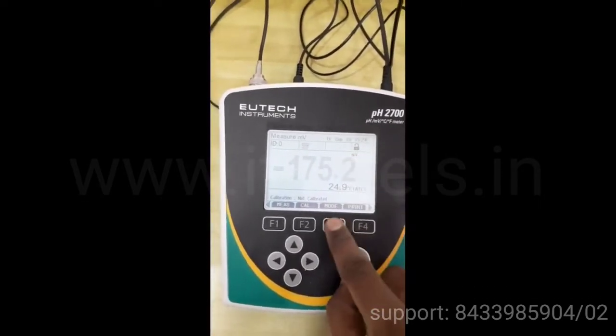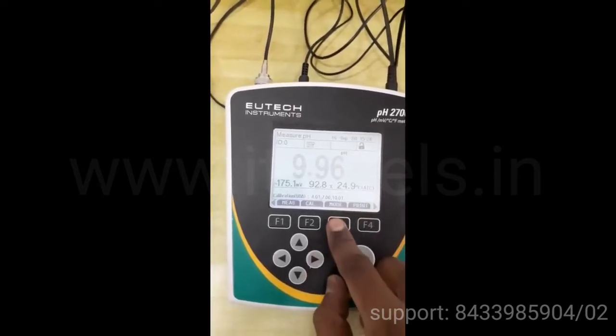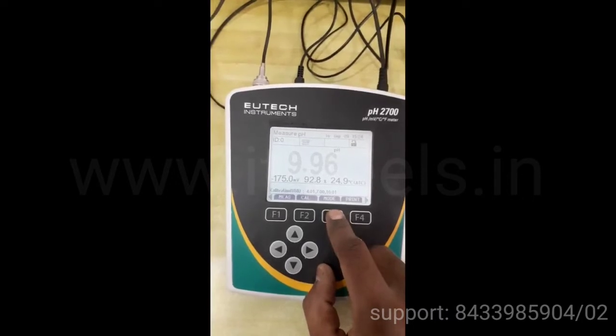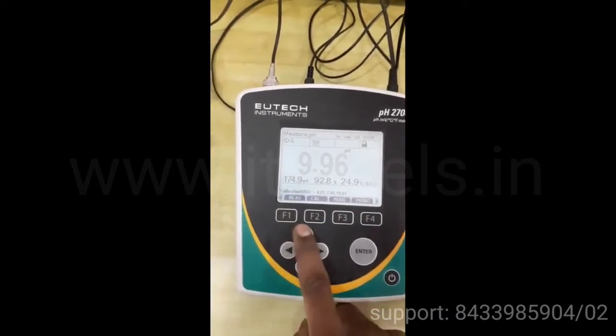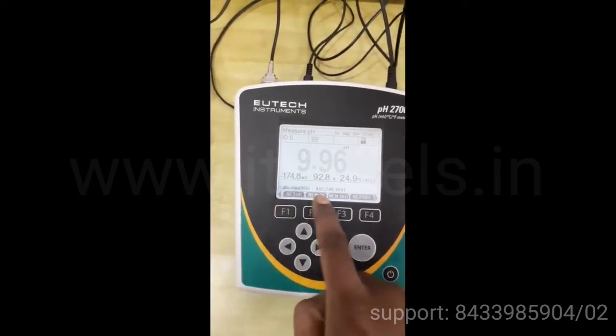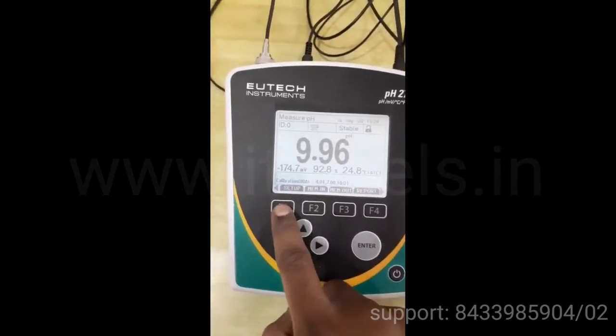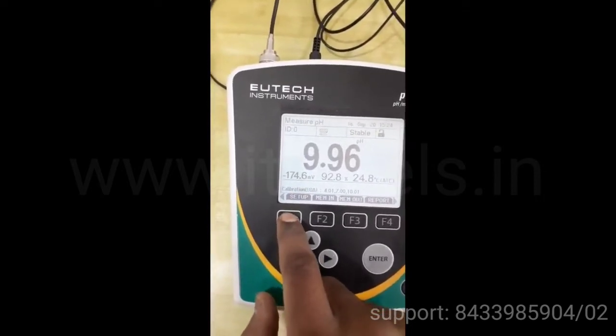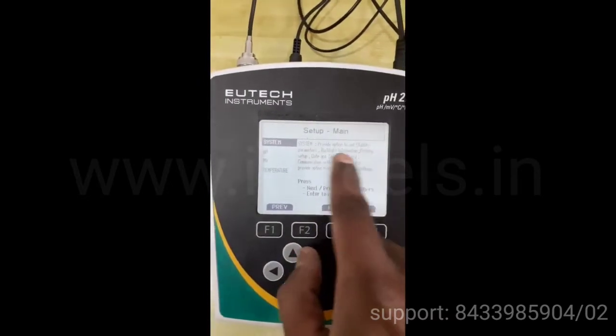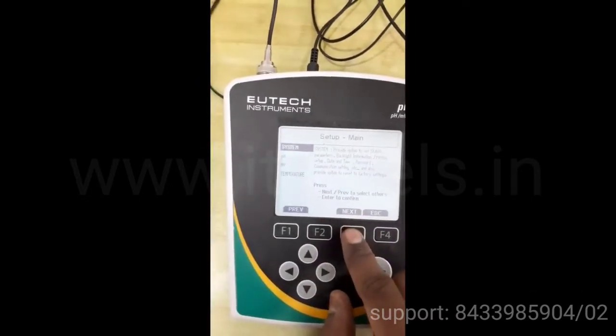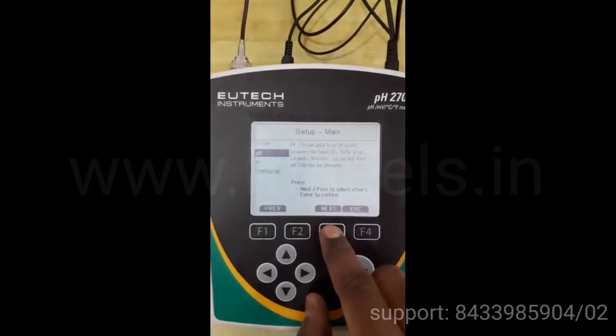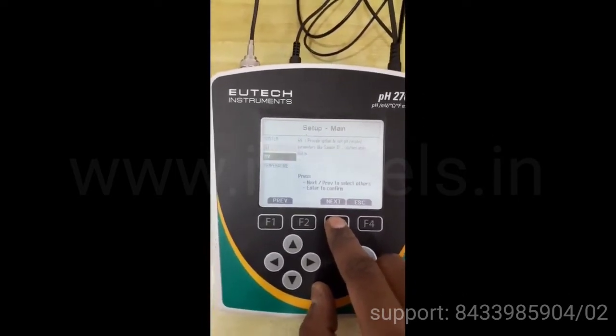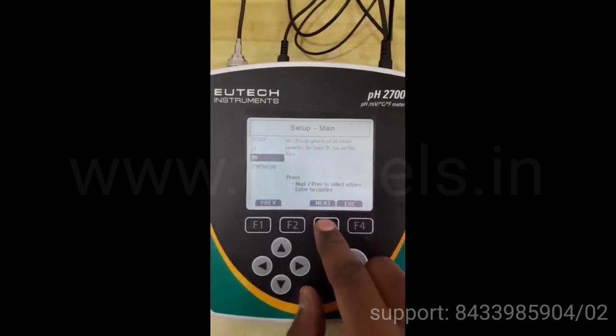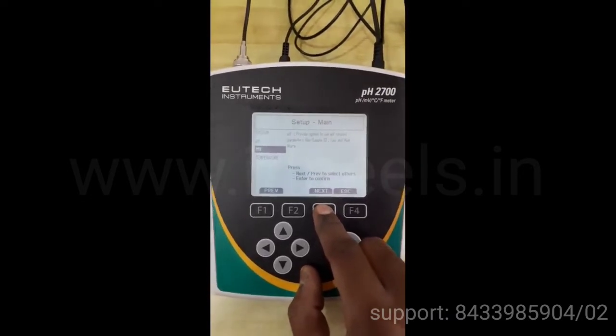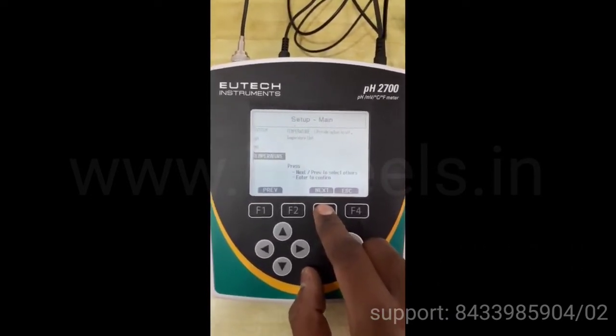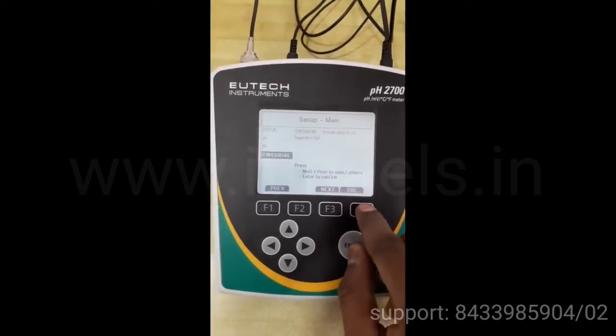Now you have to change the mode and you have to press this. Now it is in millivolts and now we are in pH mode. You can toggle between pH and millivolt by pressing this button. So to change these menus, you have to press any of these keys. Now the menus are changed. To enter setup, you have to press the corresponding button. In this you can change all these parameters: date, time, password, etc. In pH you can change the sample ID, buffer groups, calibration points, etc. In millivolt also sample ID, alarm, you can set an alarm as well. You will get an audible indication, temperature, and you come back to measurement mode. You have to press escape.